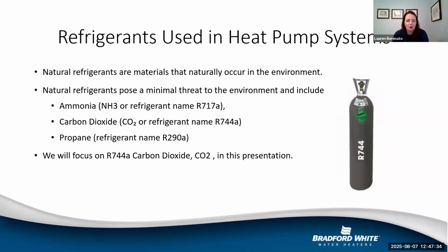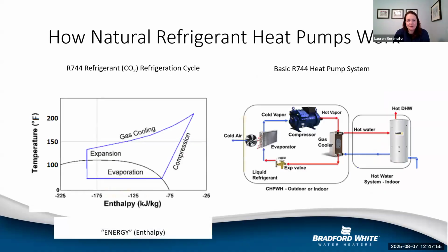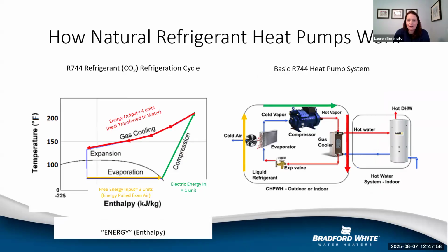And then we have R290, which is emerging for next generation heat pumps, especially in Europe, but it's just started to make its way into the United States. Very low global warming potential. However, it is flammable, so it requires very careful design. So how natural refrigerant heat pumps work, these images right here depict that. It's a little tough because some of the color on the screen is yellow. But basically it's just showing the different phase changes that occur within the heat pump, from evaporation, compression, and cooling expansion.